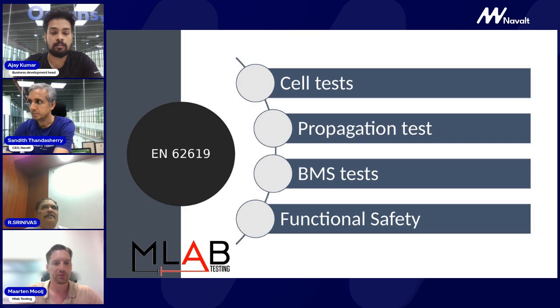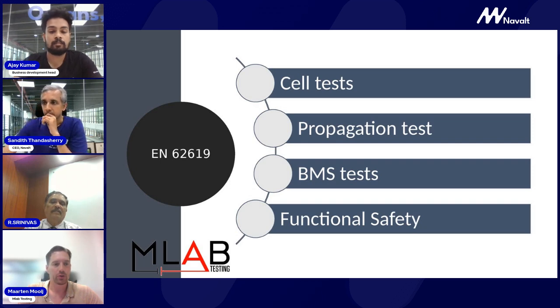These are overcharge test of voltage. So we apply a higher voltage on the battery terminals, and the BMS has to stop the charging process. And we apply an overcurrent test, where we apply higher currents than rated for the battery. And at that moment, when the BMS detects a too high current, it needs to shut down the charging process as well. And then there's an overheating test, where we put the battery in a climate chamber. We heat up the battery above its rated temperature where it can operate in. And in this case, also the BMS has to detect this high temperature and send out an alarm to stop functioning at this temperature.